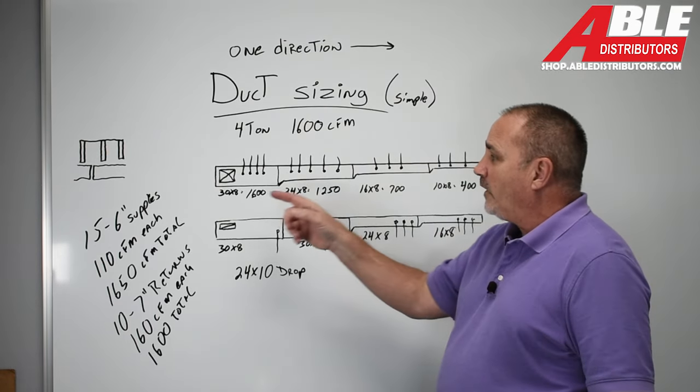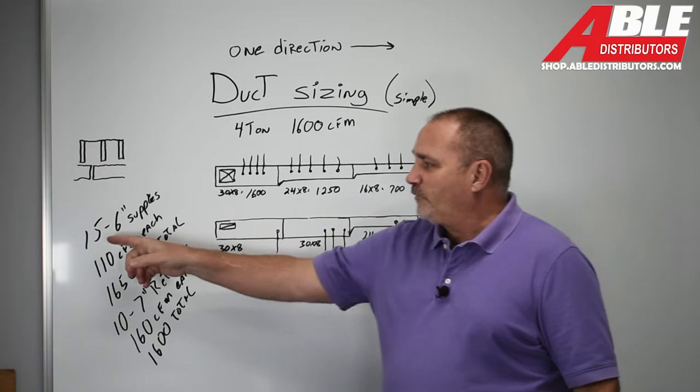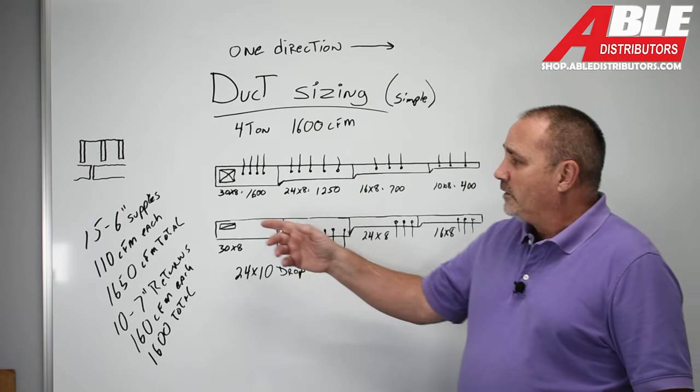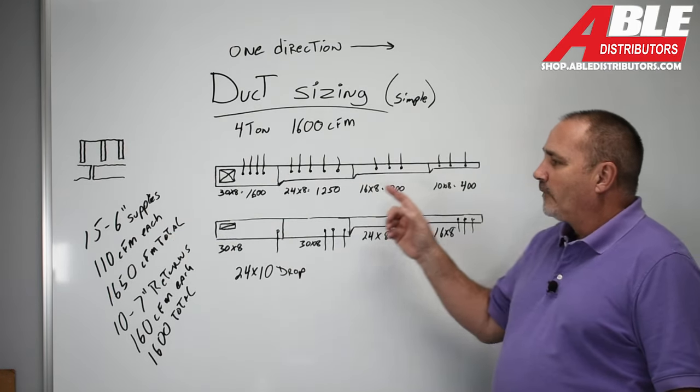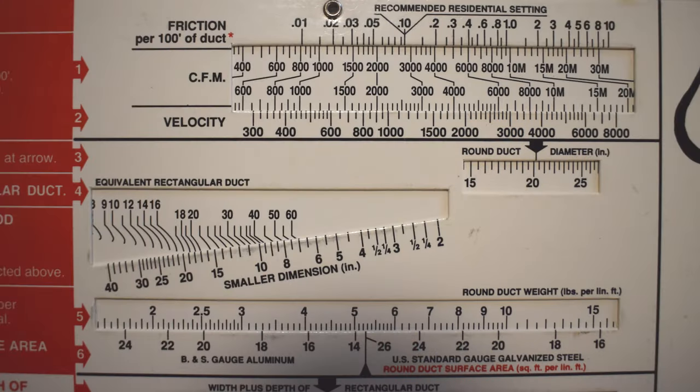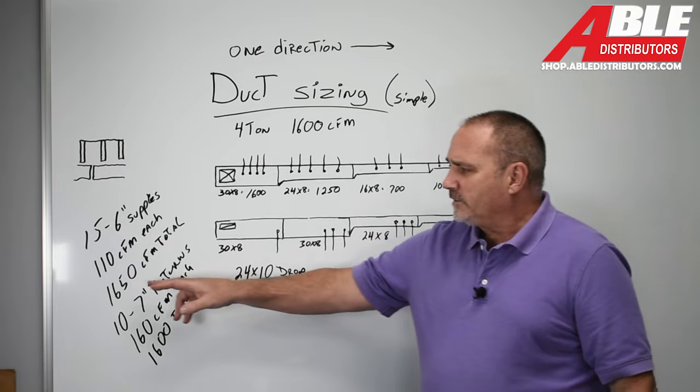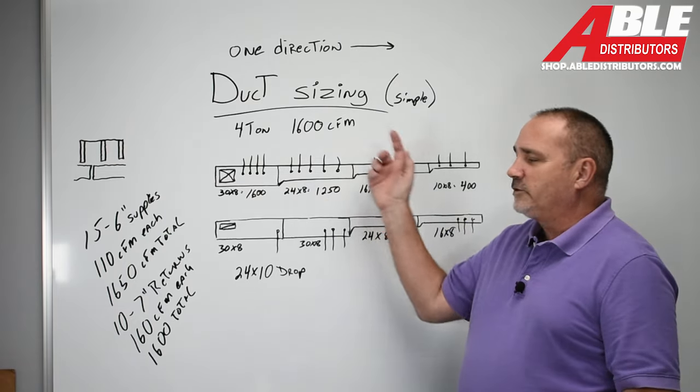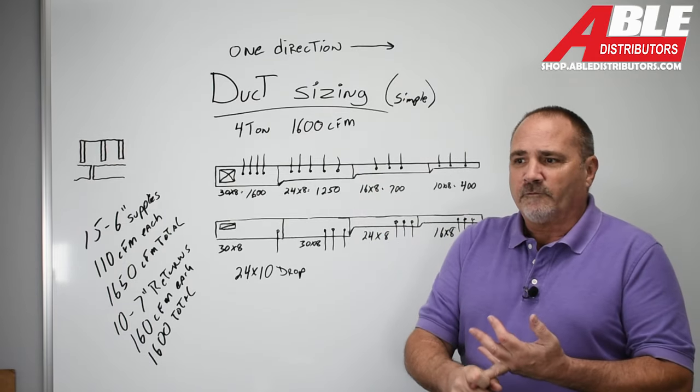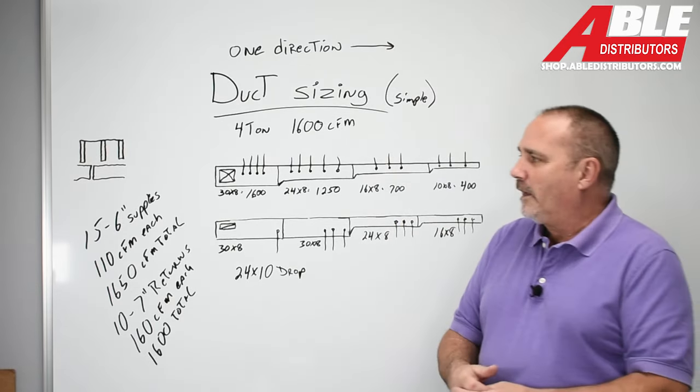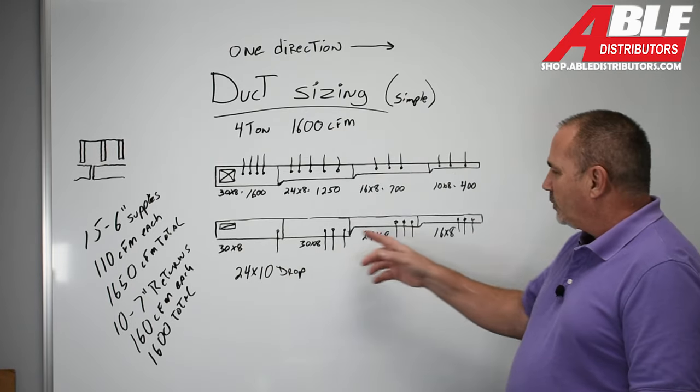1,600 CFMs. So I figured roughly 15 six inch supplies. Typically you have more supplies, more area for supplies than you do returns. So I'm thinking 15 six inch supplies, each one at 110 CFM. And I'm just going off the recommended residential setting on my duct-ulator. And again, it's a good place to start. 1,650 total available CFMs on those supplies. We know we're not going to hit it because as soon as you throw a boot and an elbow in there, the static is not going to let you get a full 110 CFM out the other side. So that's fine.